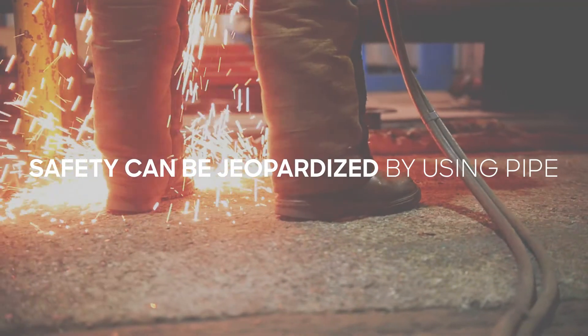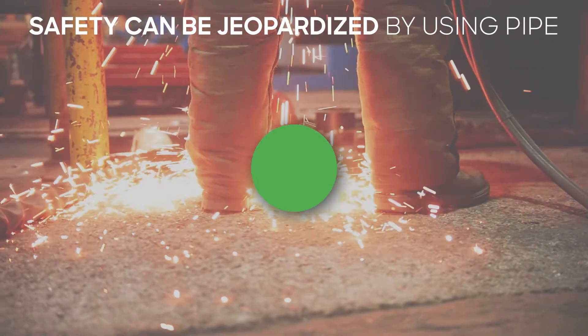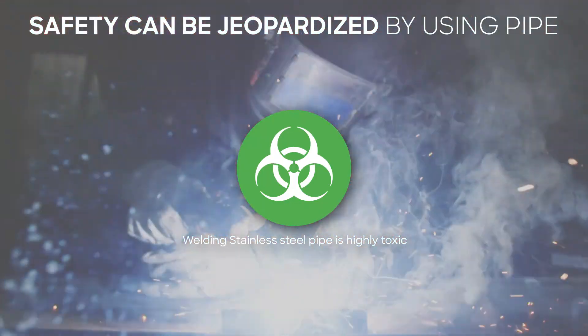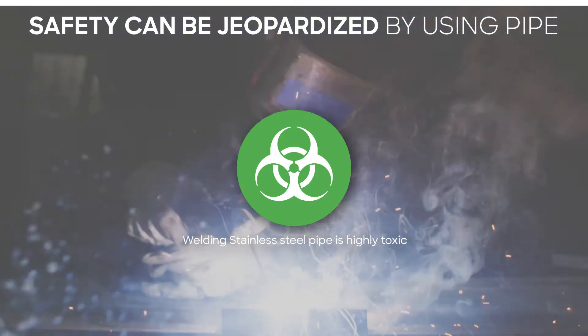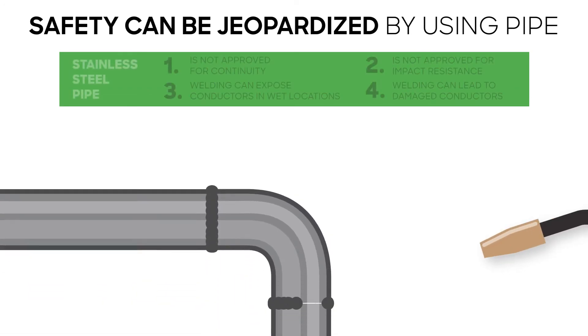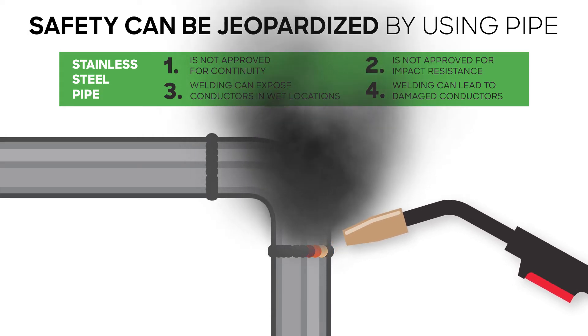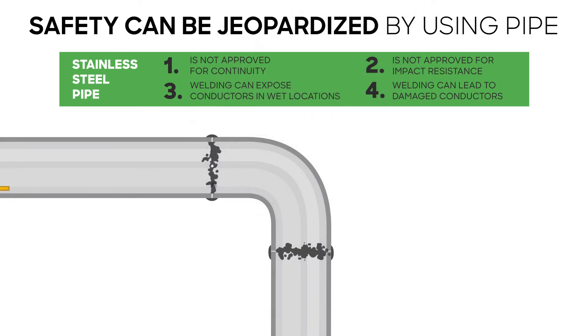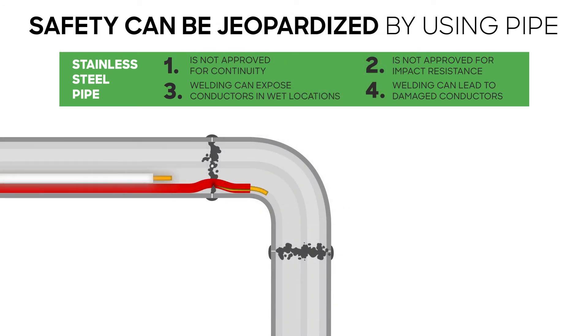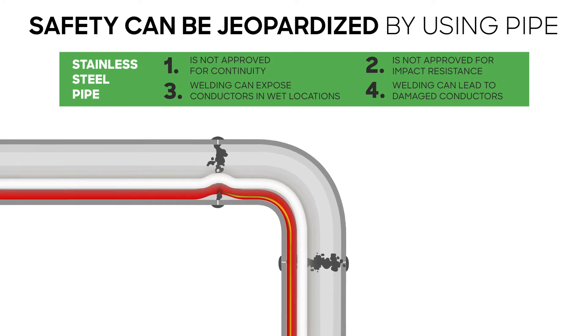The biggest reason not to use welded stainless steel pipe instead of conduit is safety. Welding stainless steel pipe is highly toxic and exposes the welder and people nearby to carcinogenic chromium-6 fumes. However, there is no greater risk than electrical safety gone wrong. Using welded pipe not only violates the NEC but causes significant safety risks. Stainless steel pipe interior and exterior surfaces often contain metal trimmings, hard scale, burrs, sharp edges, sharp projections, or other imperfections which can damage wire or cable insulation during pulling.